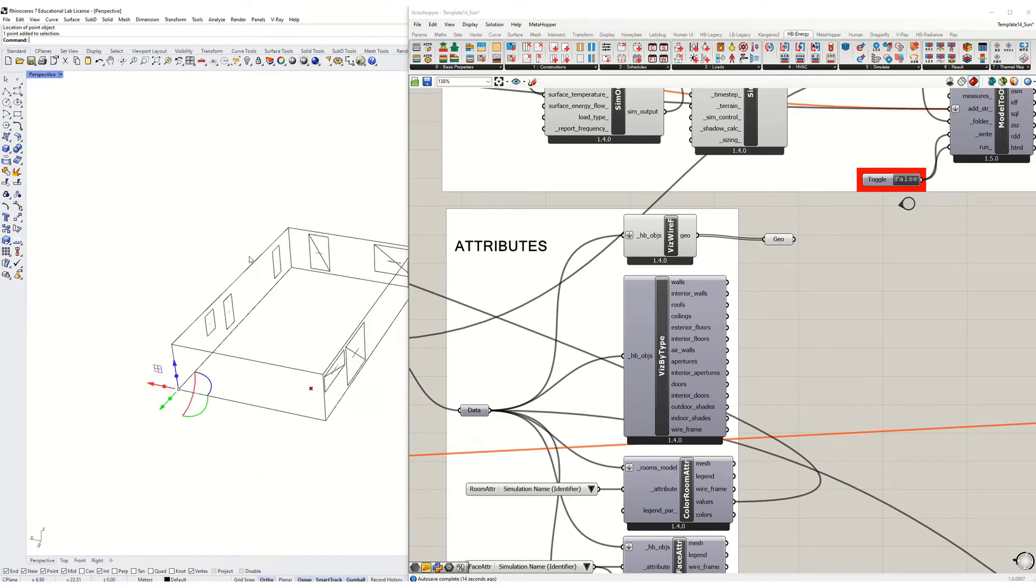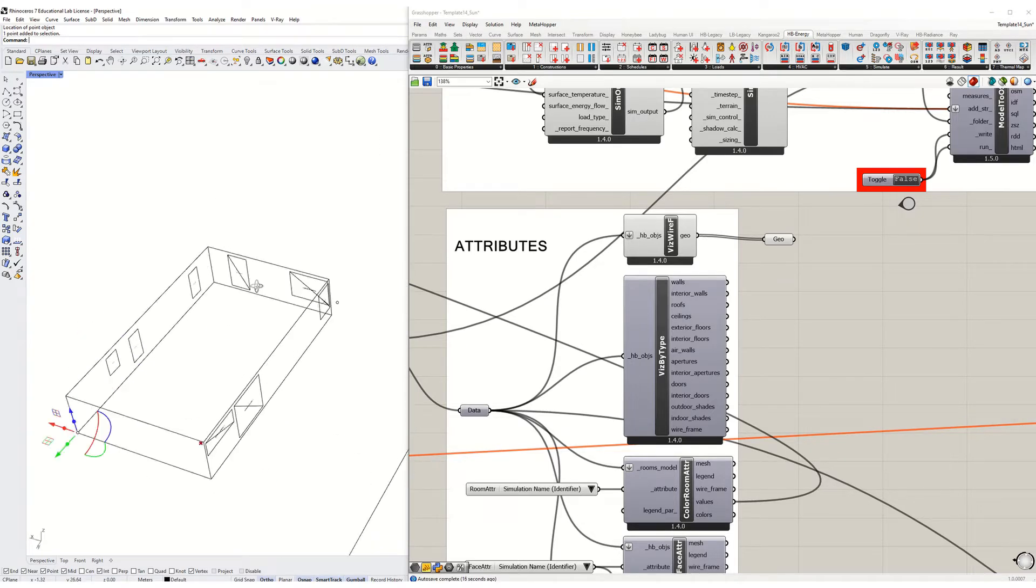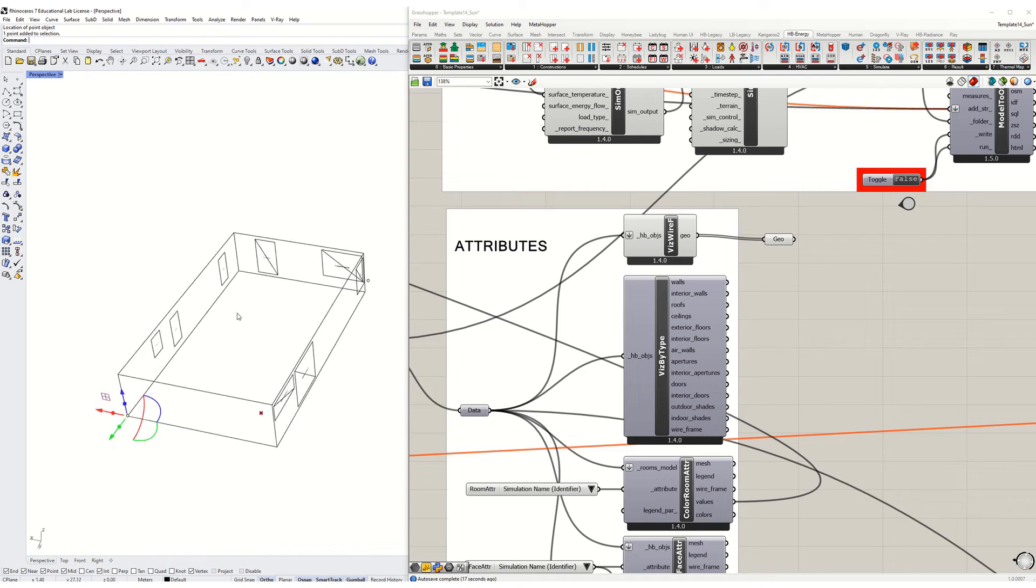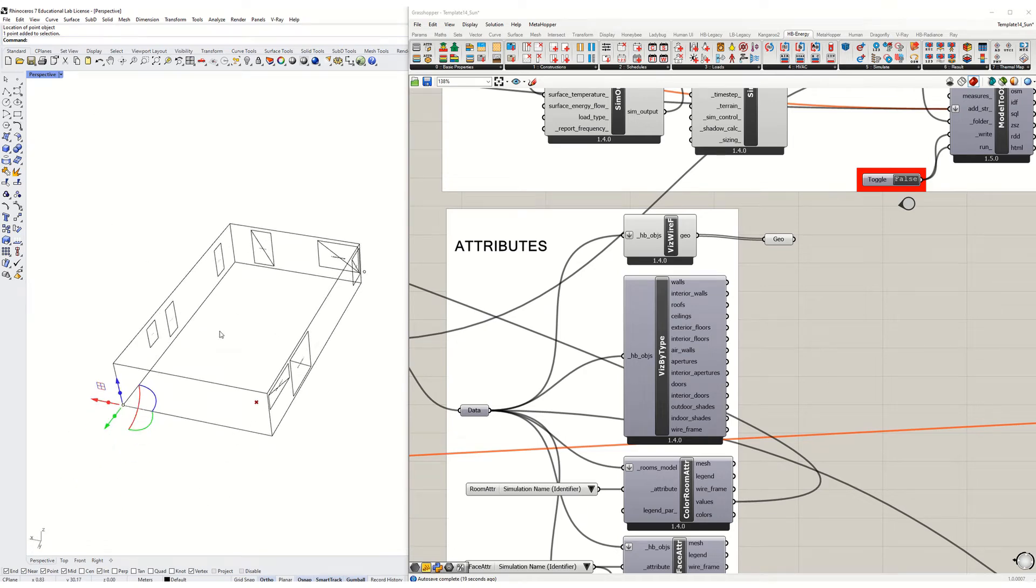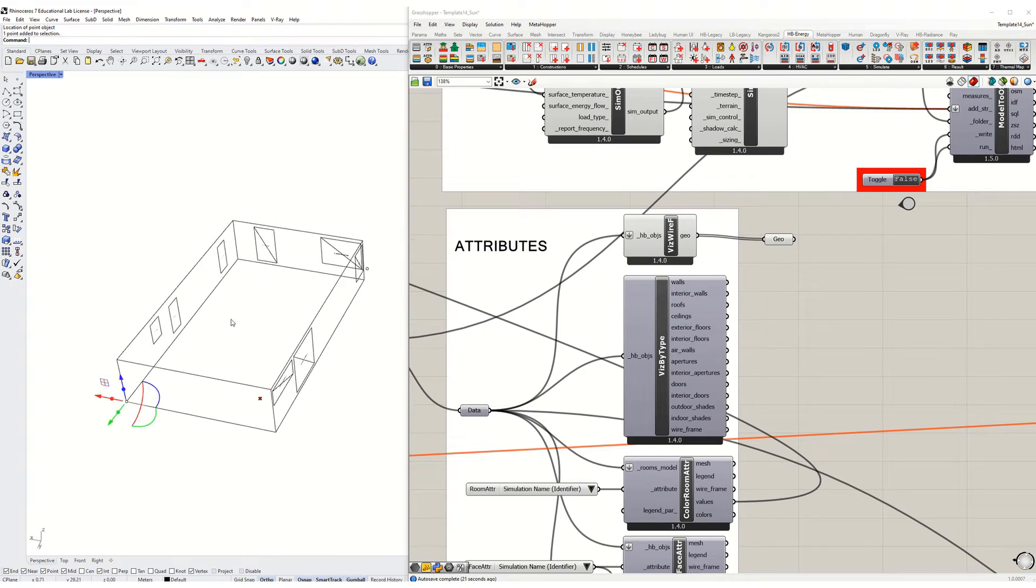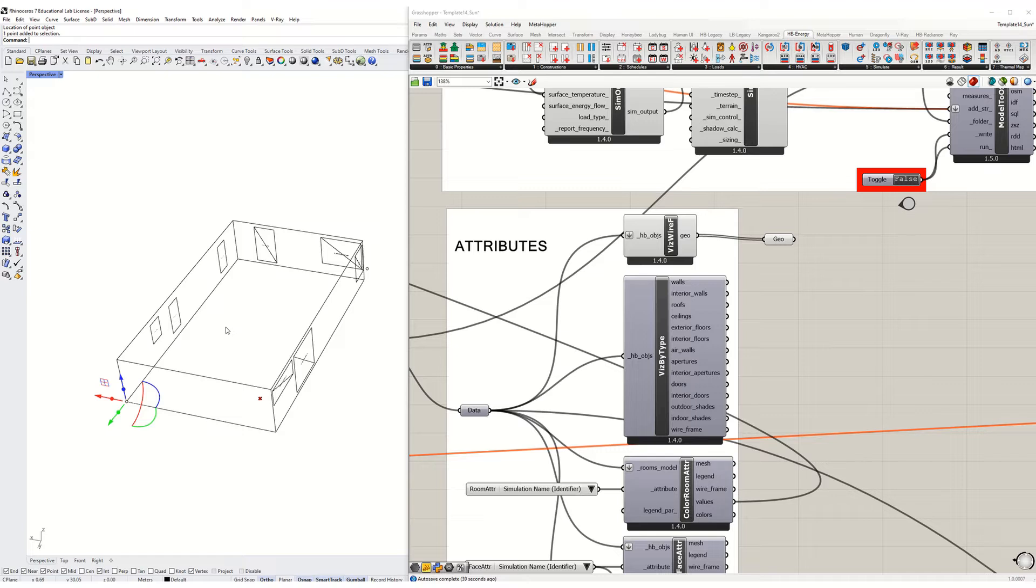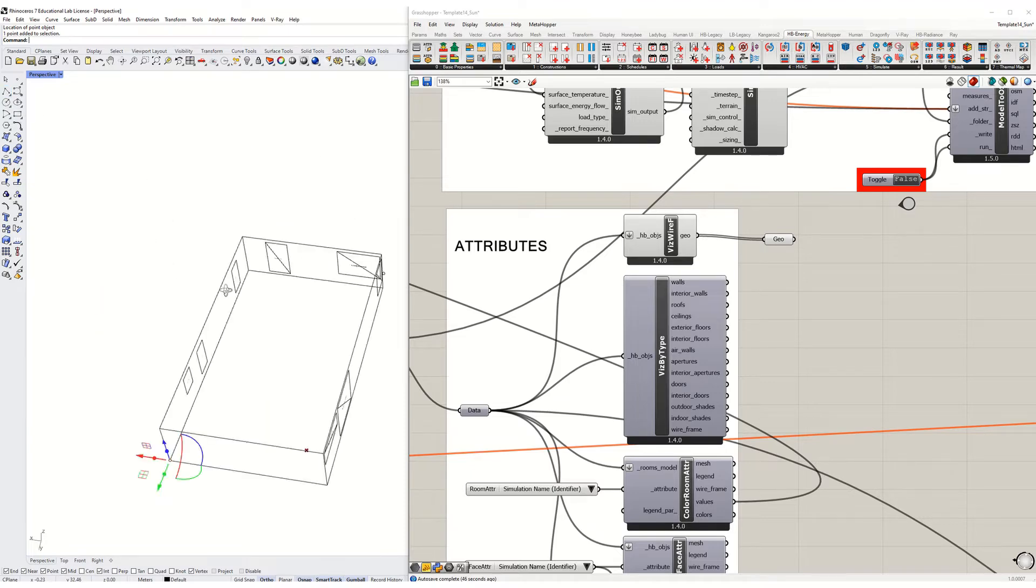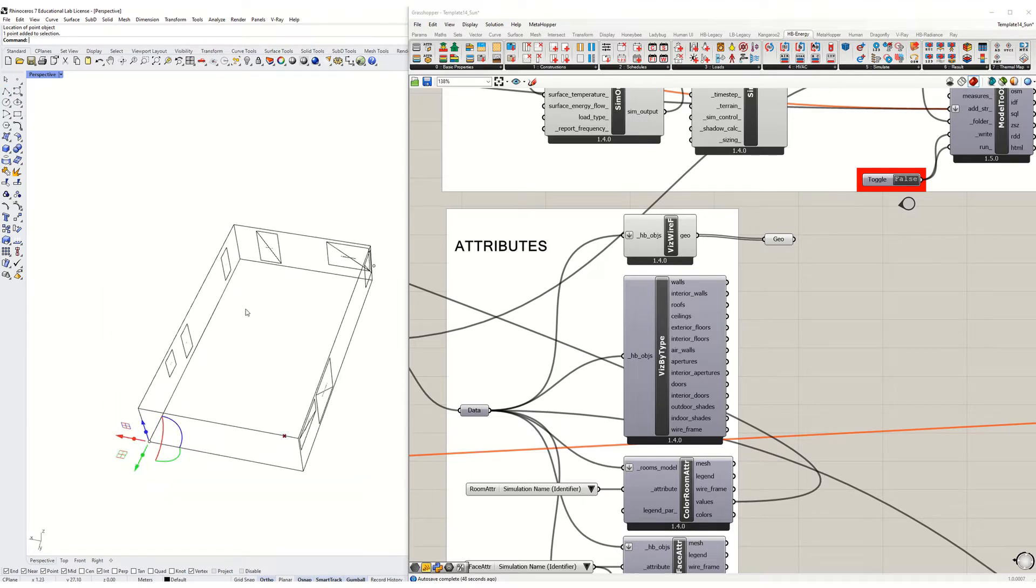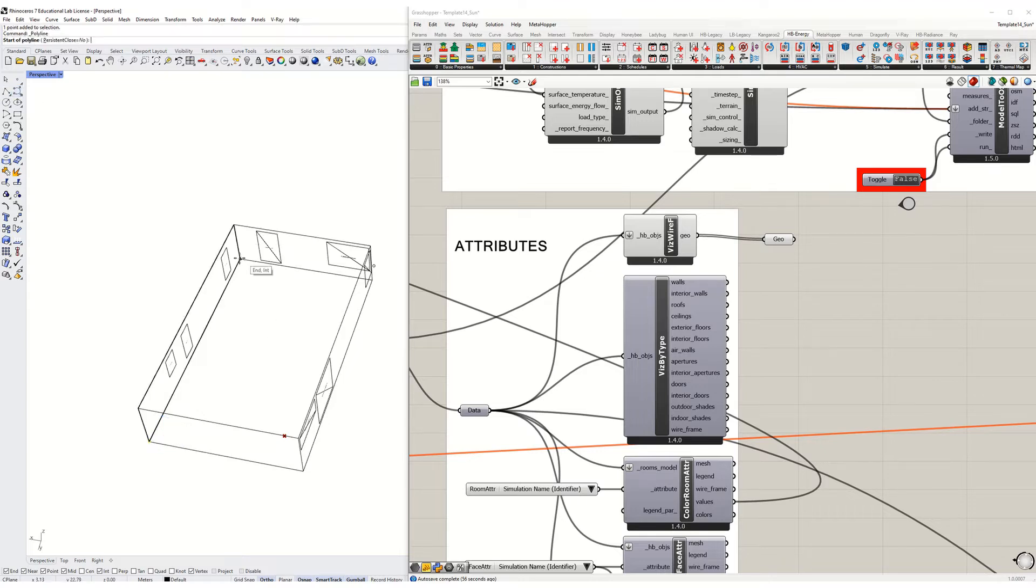Now we've got glazing all the way around here and that glazing will allow daylight in and the electric lights should probably be able to be turned off for much of the day, much of the year. What we want to do is locate the sensor point for the daylight dimming at the darkest part of the room so that we make sure that we've always got enough light for someone to see. And in this particular zone, I would probably estimate that the darkest part of the room is either somewhere along in this corner here or kind of in the middle of the room here. I'm going to just assume that it's in the middle of the room for this.